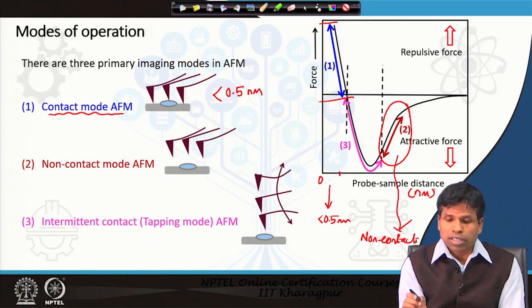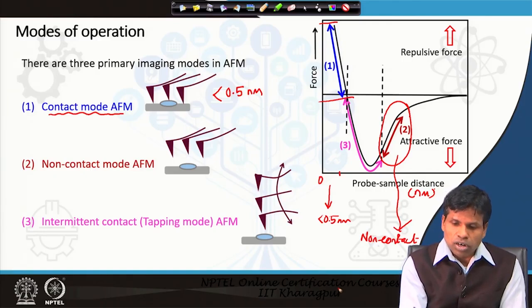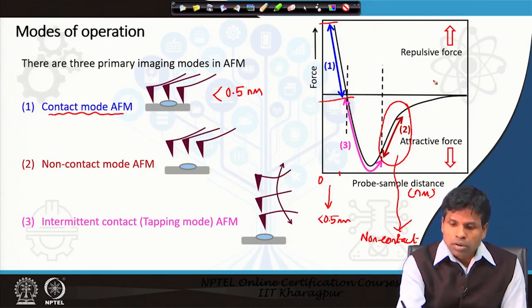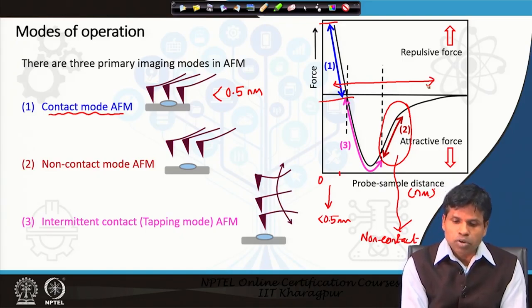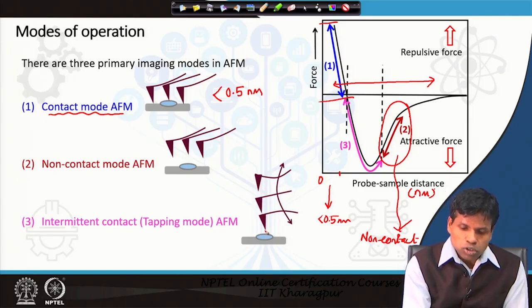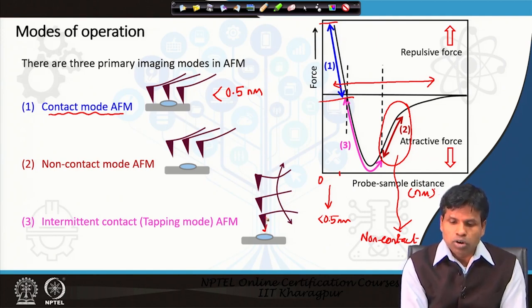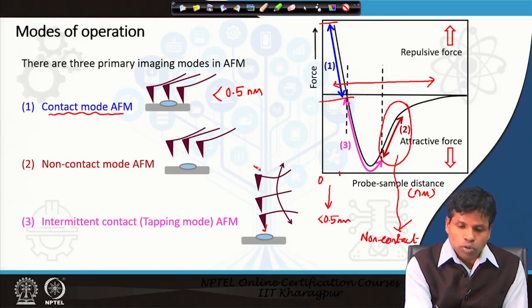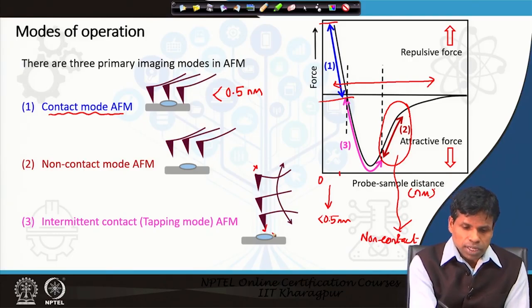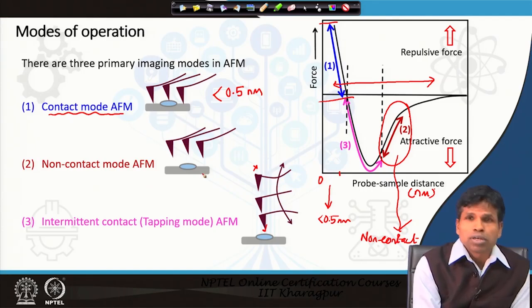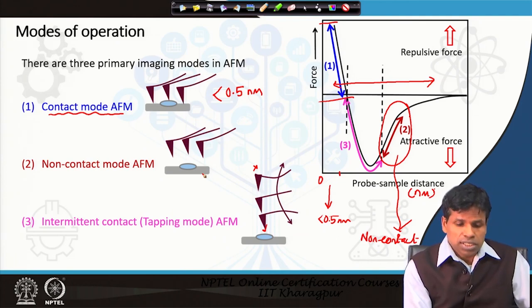Between contact and non-contact mode is the intermediate region called tapping mode. The tip goes from the attractive to the repulsive region — it goes close to the sample into the repulsive force region, then goes back upward where there is no force, oscillating forward and backward above the sample. This is called intermittent contact or tapping mode. In non-contact mode the tip-sample separation is more than about 2 nanometers, where attractive force predominates.